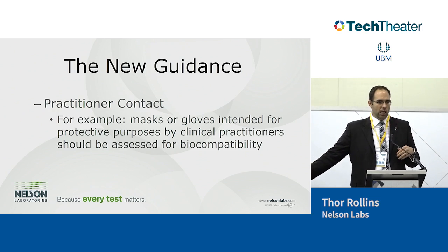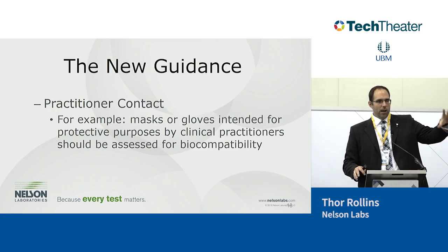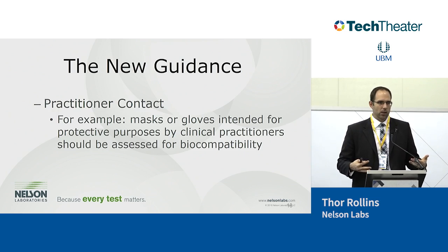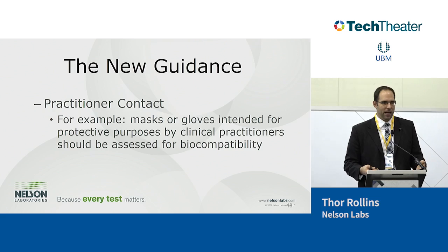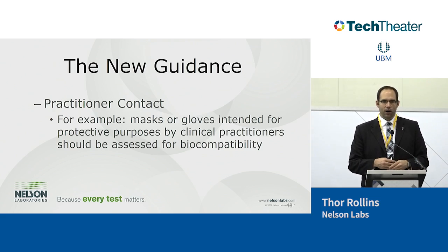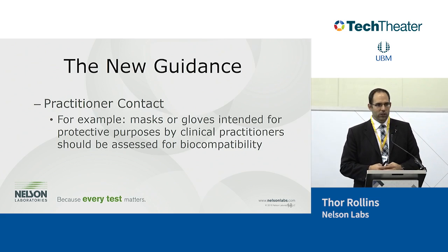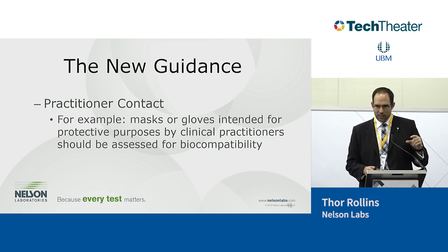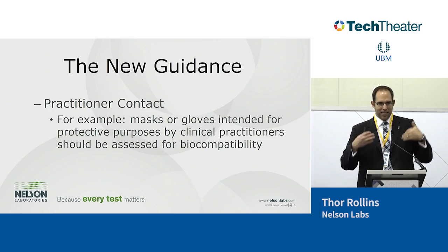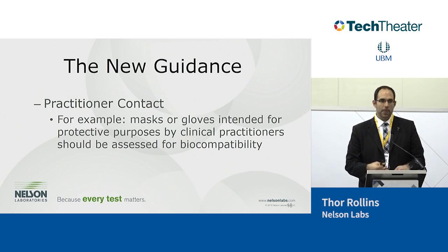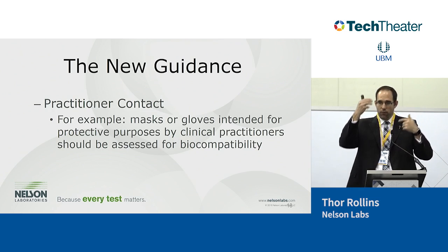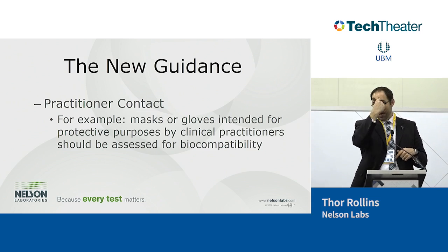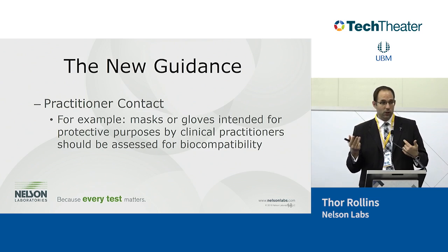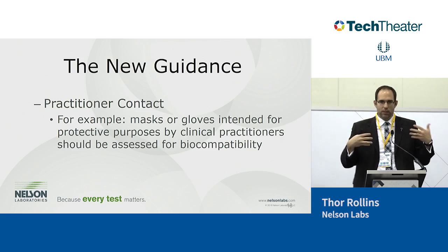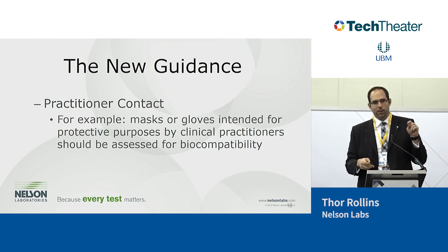This first one is practitioner contact. When we talk about practitioner contact, a lot of people get freaked out because they're like, man, my surgeon touches the handle of my device, and I've never tested the handle of my device. So now do I have to start assessing the handles or whatever could be contacting the patient? The document is specific for type of contact that is not protected. So like the doctor does not have PPE. The one that we just did recently was a headband for a face shield of the surgeon. So the headband contacts the surface of the skin of the surgeon, and he doesn't have gloves or a sheet protecting him. So we had to assess the biocompatibility of that headband.